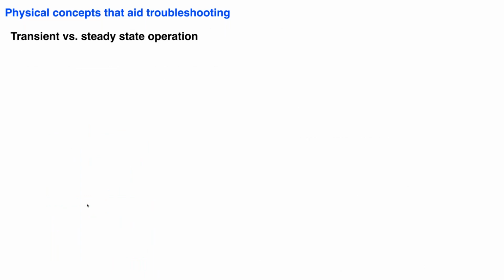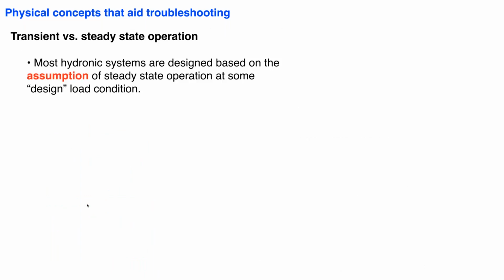And then finally, transient versus steady state operation. Now, when we design hydronic systems, we're usually designing in what I call a snapshot condition. We're making an assumption that the system is operating at steady state conditions at some design load condition, which usually corresponds to the coldest day of the year. What is our system doing? What is our flow rate? What is our BTU per hour heat transfer rate?